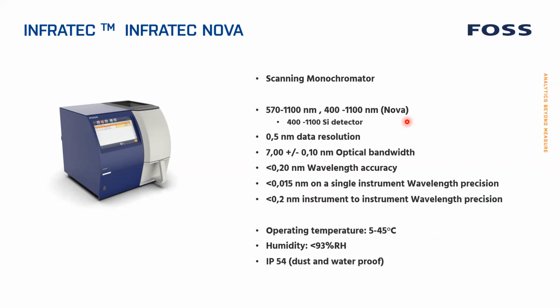And in principle, no one is doing the wrong calibrations for Infratec. 0.5 nanometer data resolution, and the optical bandwidth is 7, so it's a little sharper here than on the DS. Otherwise, wavelength accuracy and precision are the same, so it's 0.2 and 0.015 on the precision. And it goes the same here. If you do a calibration on one instrument, you can move it to a second instrument and you get the same result.